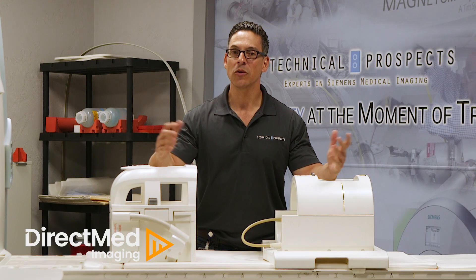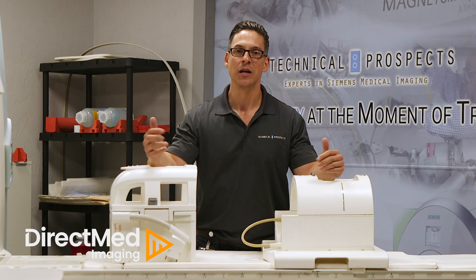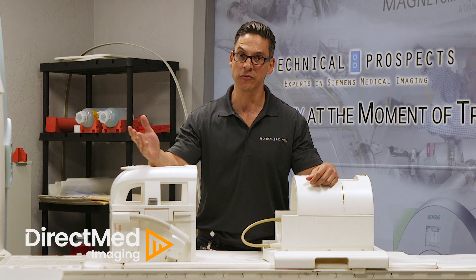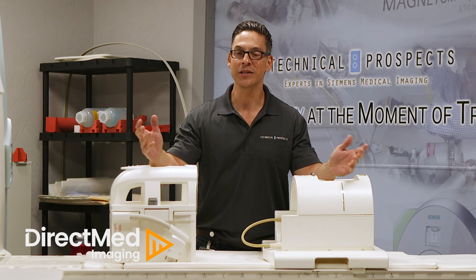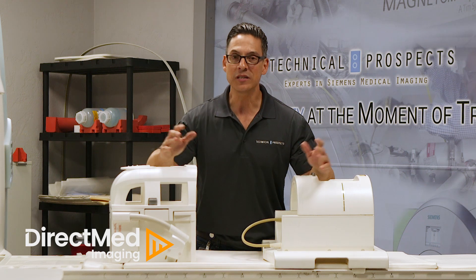Today I'm going to show you the difference between a transmit-receive coil versus a receive-only coil before positioning for a patient. A common question I get asked as an application specialist is how can I tell which one is a receive-only coil and which is a transmit-receive coil? A lot of people think that the head coil is a transmit-receive coil, and it's not.